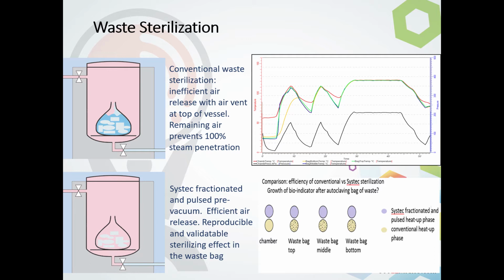So it will, at that point, start creating some steam from the heaters inside of the unit. It's going to then compress all of the air into the bag, so we have a nice little pocket for things to continue to grow inside of that waste bag. Now, with the Systec fractionated and pulsed pre-vacuum, we're going to pull that vacuum before the cycle starts. We're going to run it very similar to the instrument sterilization, and we're going to be able to achieve the exact type of steam penetration that we want to that bag.